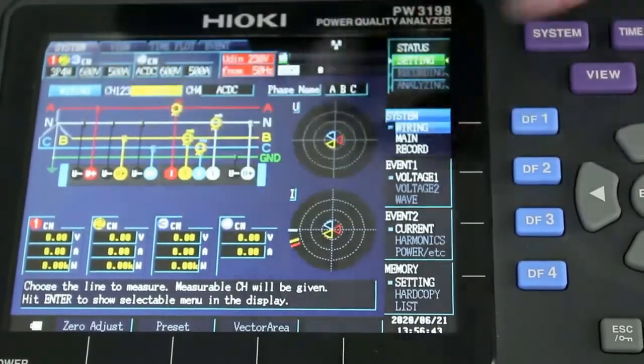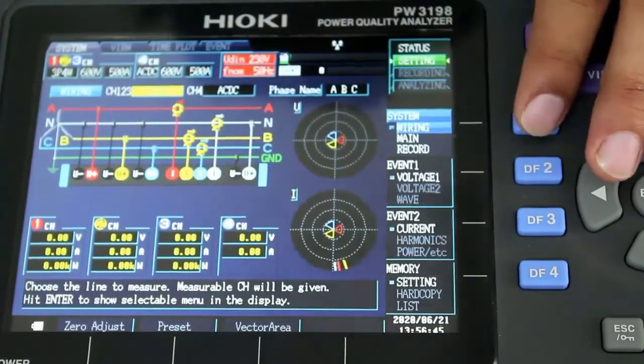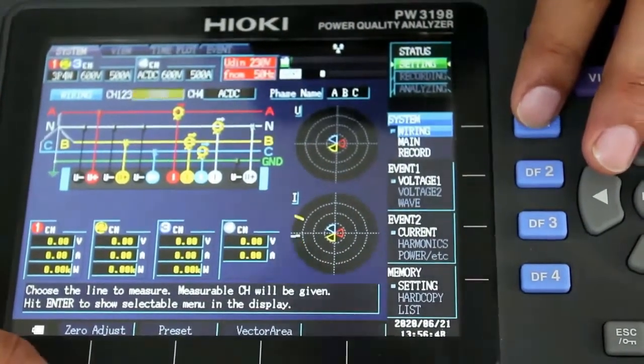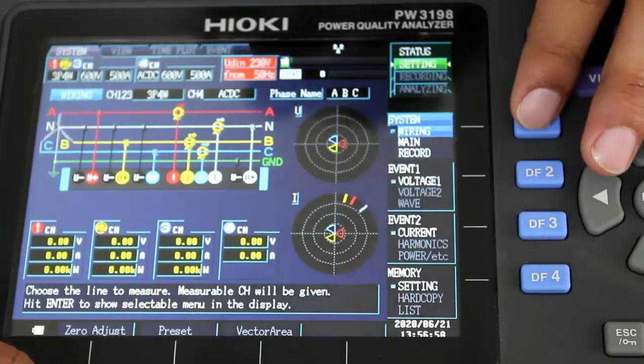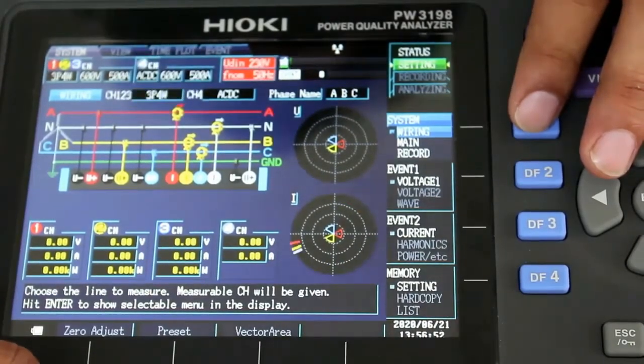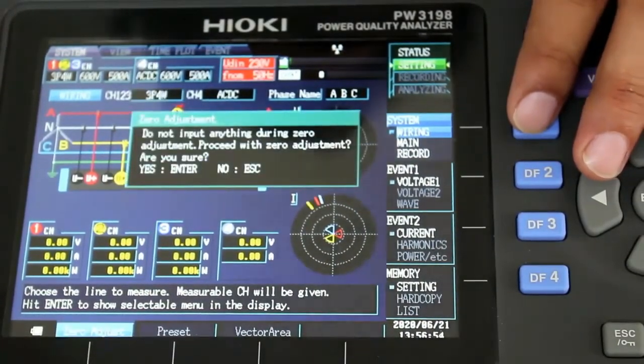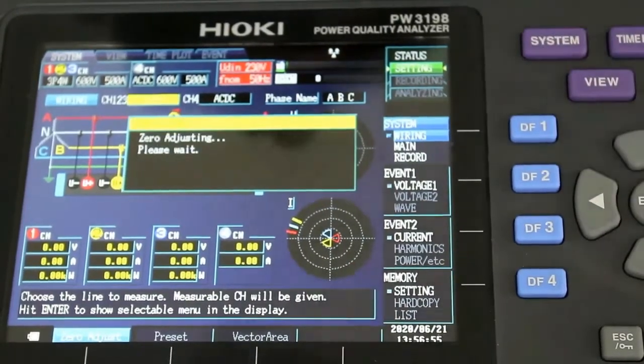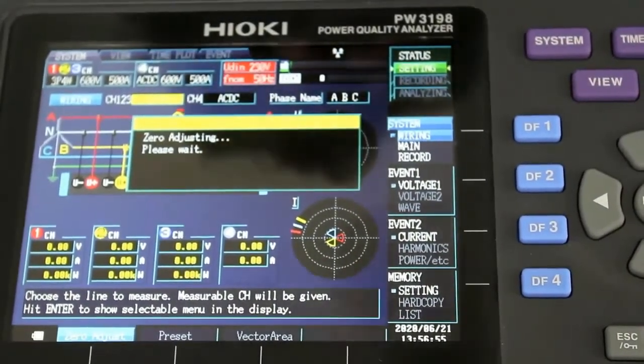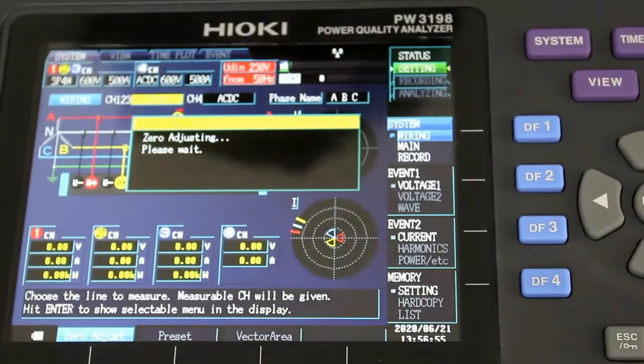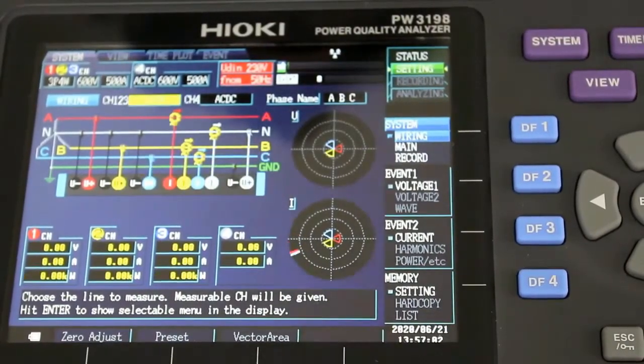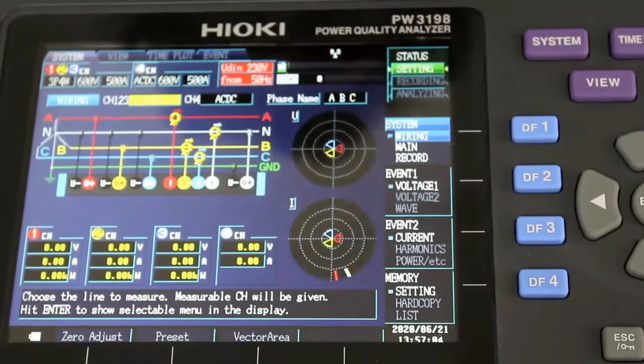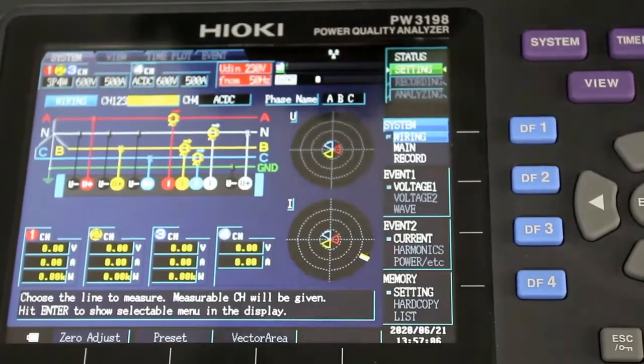Now this is a wiring setup method. Below there is a zero adjust method. After doing the connection, if you want to do the zero adjust, you can press it like this and press enter, and then it will do the zero adjustment for us. Whatever the noise in the voltage and current, it will suppress all those things.